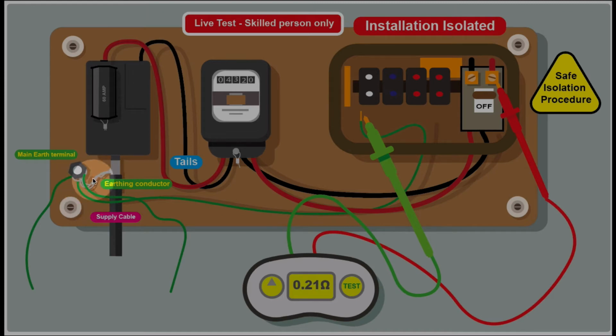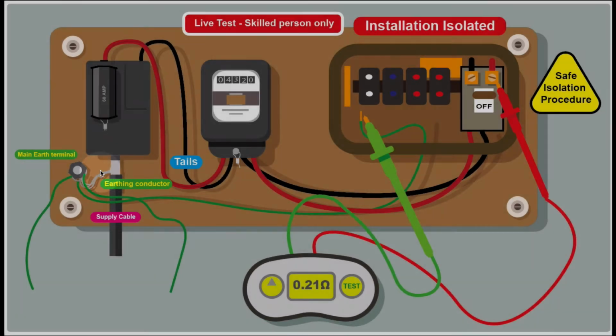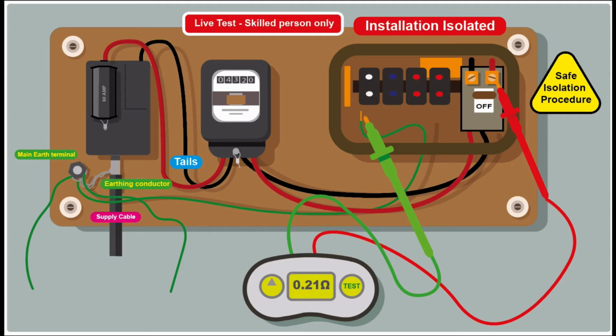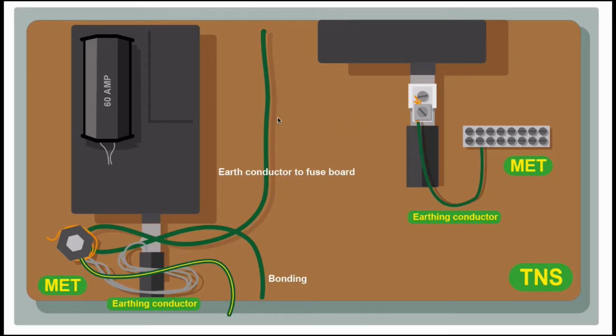What we want to confirm is the earthing conductor here, our ZE. So we can't test it from here because we've got these connections. So we need to disconnect this and just get to the earthing conductor here. Okay, in our setup, we've got an old-fashioned type main earthing terminal. It's like a nut and bolt, where all the various conductors are brought in, twisted around each other and tightened with a nut. We can't individually remove the conductors like you can with the earth bars. You can just undo that screw, pull that conductor out. So we need to remove this and replace it with one of these.